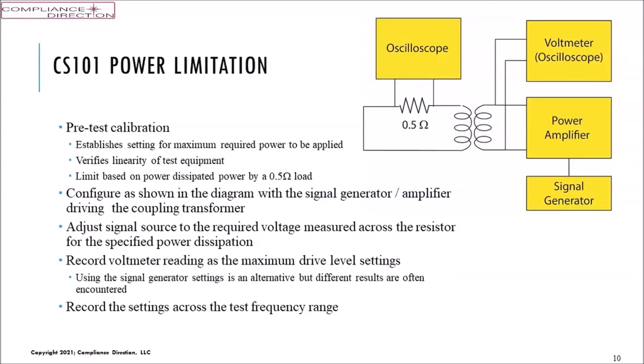The next question, and thank you for that, is also a lengthy question, so I'm going to try to break it down as I read it. For calibrating the 100 kilohertz signal, when I inject the output power of the signal generator set to -6 dB of the limit, which is converted to -39.1 dBm, or 2 mV RMS, to the power output of the LISN, the oscilloscope measures the signal at 24 mV RMS. The question is, should I be calibrating the signal before connecting to the power output of the LISN?